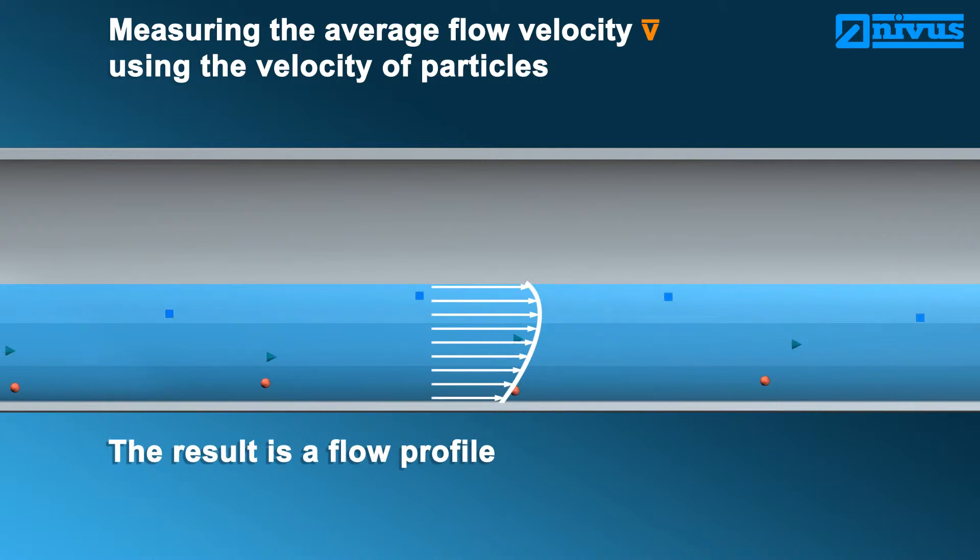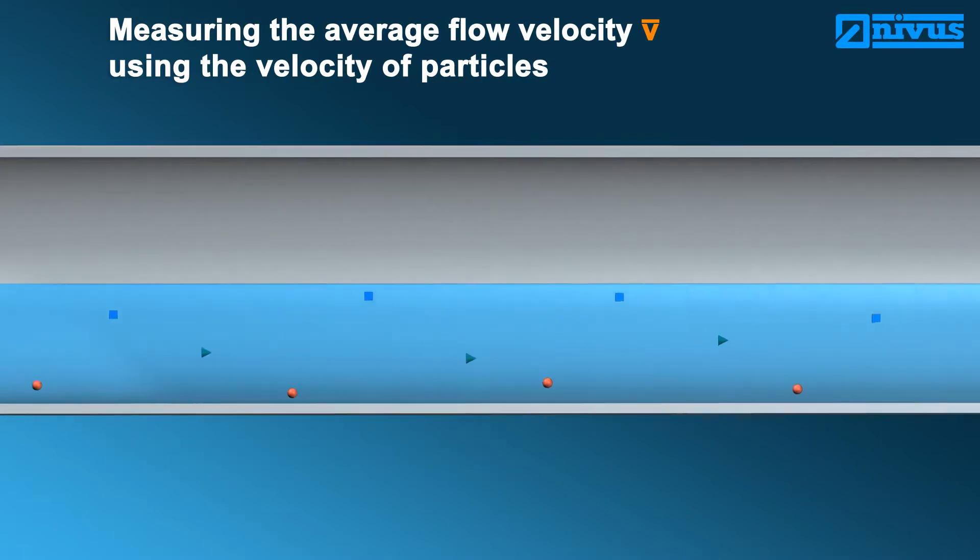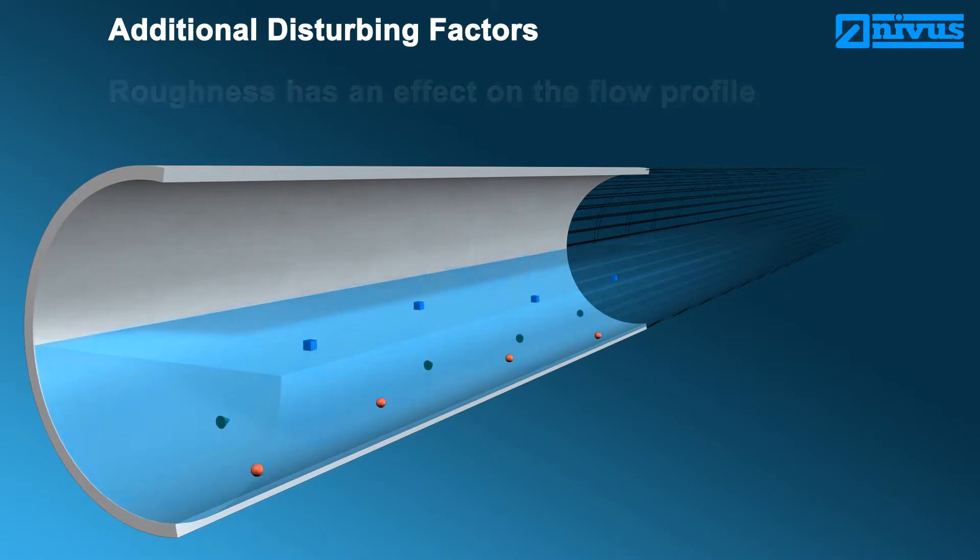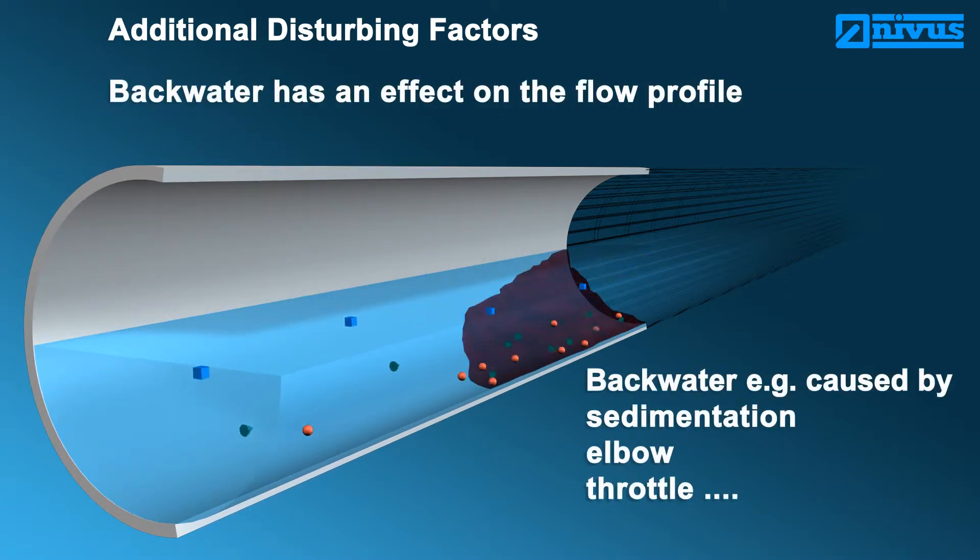This profile depicts the flow velocities related to the levels. Miscellaneous factors affect this flow profile: disturbing, free discharge, or may result in the formation of backwater. Such disturbing factors may be pipe roughness and varying sedimentation, solid concentration, or influences due to construction such as elbows and throttle equipment.